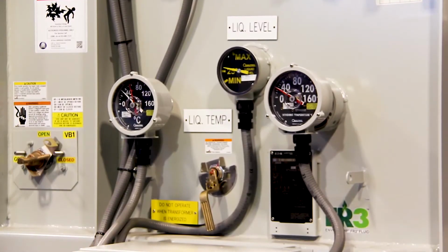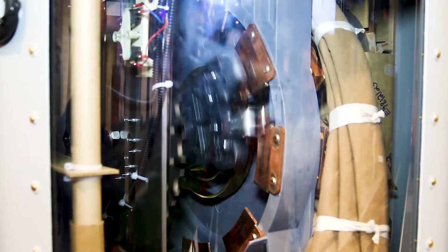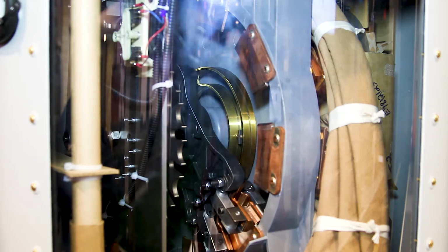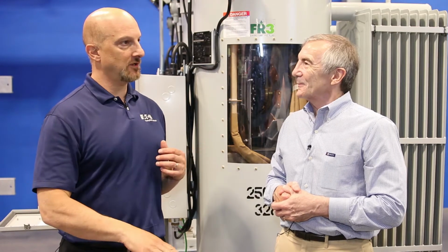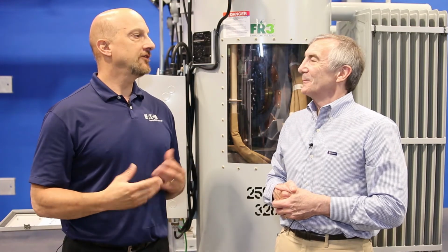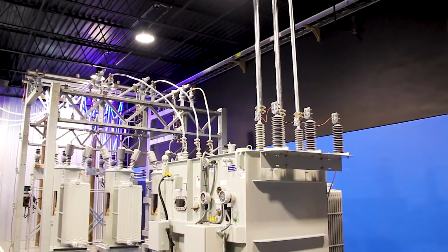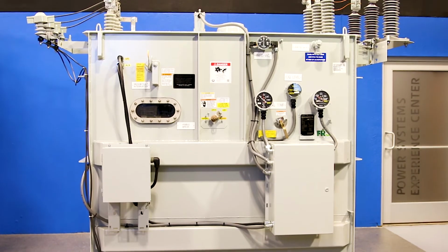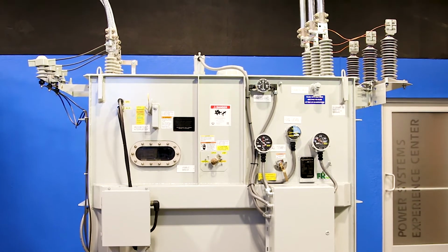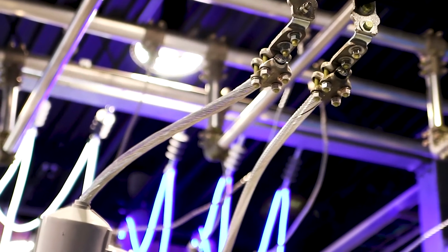So these things that we're standing right next to are regulators, and the regulators get a little bit confused. Do I need to go back up or do I need to go back down? Then a cloud comes by and the solar goes away and the regulators are low and the voltage is all over the place. So we have issues with three main components. One is the capacitor banks that supply the reactive power to maintain voltage stabilization. The other is the regulators that truly regulate the voltage. And the third is the capacity of the transformers and the other equipment, the wire sizes and so forth. They're rated for a certain amount of current, and the more we put into the substation, we may put more current in than they were even rated for.